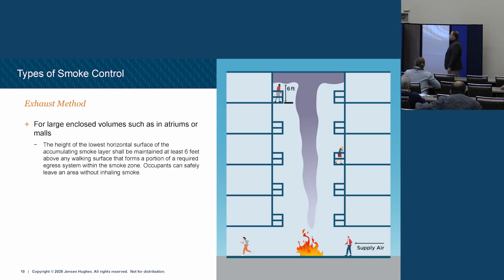All right, so let's talk about what the different methods are. And this is where you might see, oh wait, maybe I do have that in my building. So the exhaust method, I briefly talked about that with atriums. We bring in the supply air down low, and we pull that smoke out at the top, and the objective is to keep that 6 feet above the top occupied floor. It would be more than adequate for me. For some of you, you might be head in the smoke, but for me, I'm way under that. So that's the objective, right? We're looking to keep the smoke out of the occupants' faces and leave it a tenable environment so they can get out of the building.